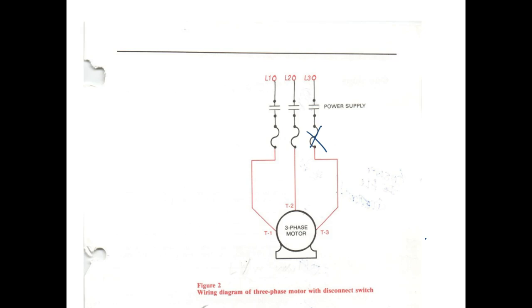You're going to try to measure your voltage on that. 3-phase is kind of weird. So what would you think if this phase right here opens, and I came over here and measured these phases with a voltmeter, with this phase open? What would you expect it to measure between T1 and T3, where T3 is open? T1 and T2 is going to measure fine, right? You understand? But if I go from T1 to T3, or from T2 to T3, what would y'all expect to measure? Go measure that.